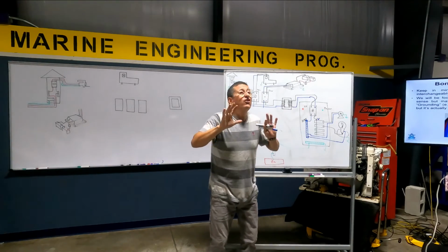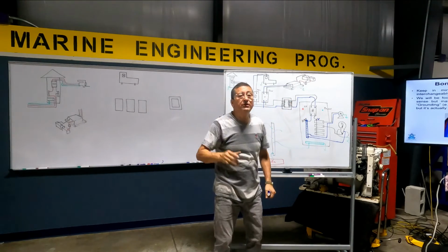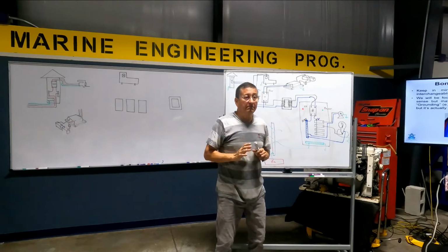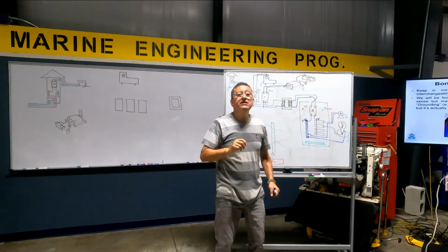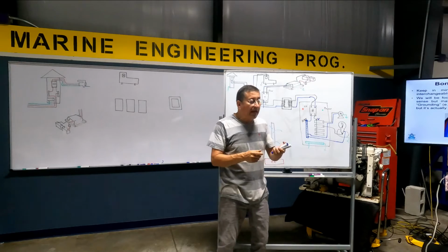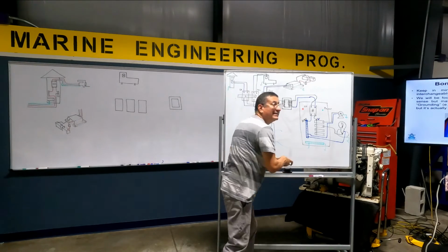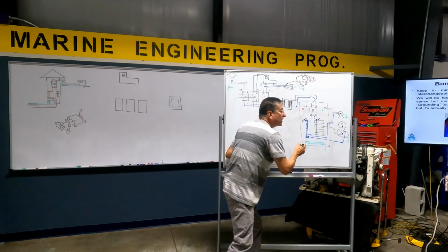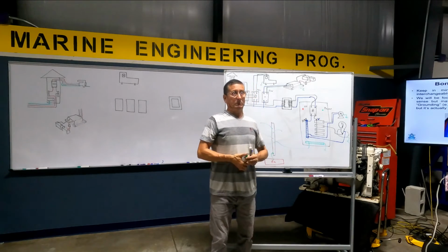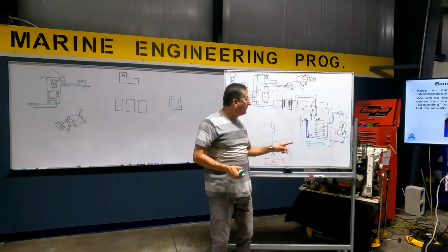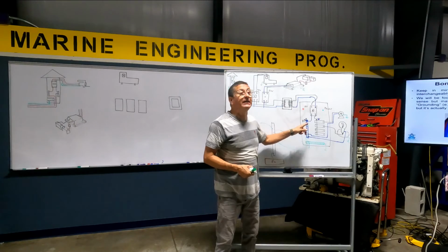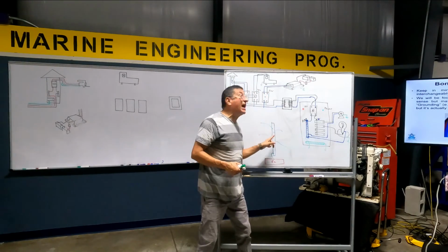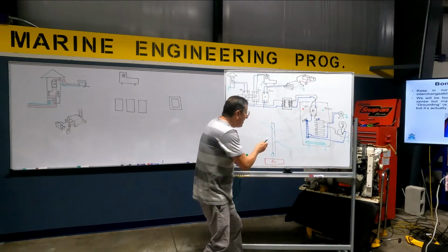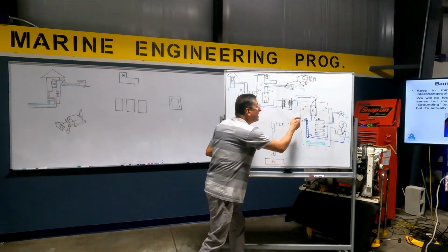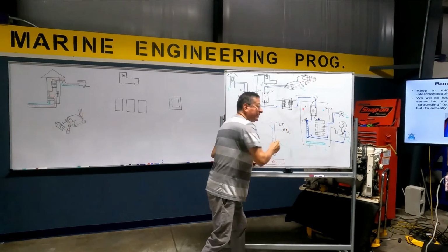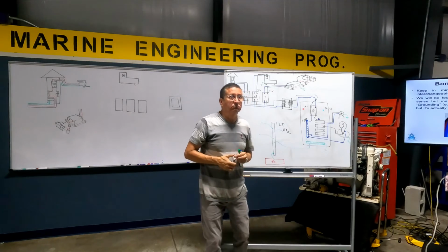What happens if, for some reason, an electrician — not a marine electrician — installs equipment on your boat and decides to connect neutral together with ground? What happens at that moment is you have reverse polarity. What happens to your ground bus bar and your bonding? How much voltage do you have in your bonding? 120 volts, 60 amps in your bonding conductor.